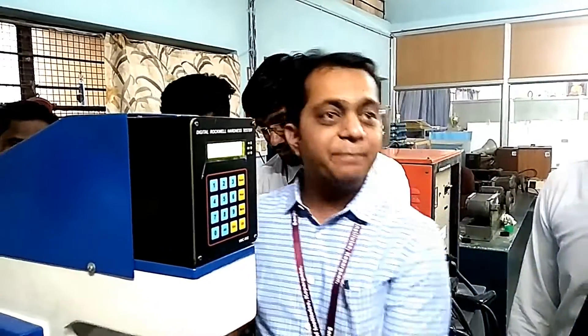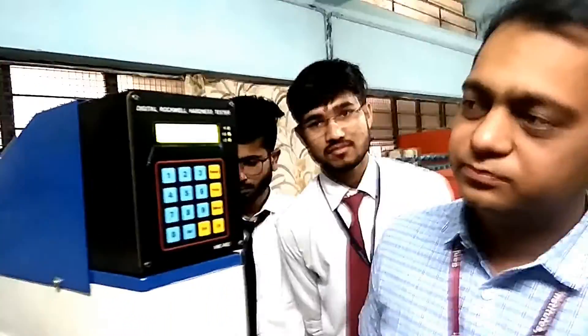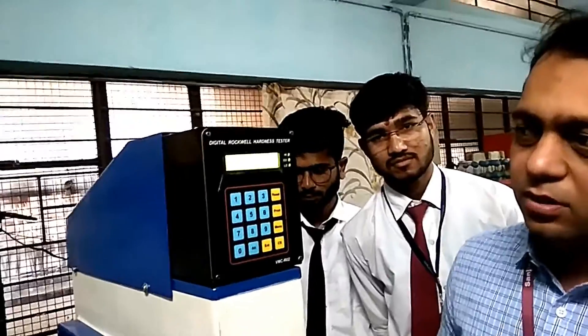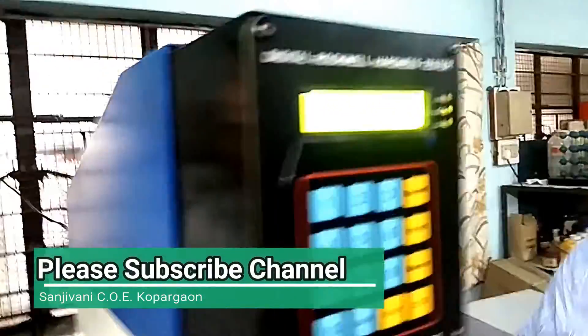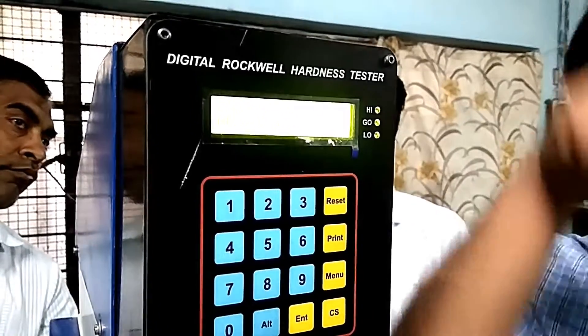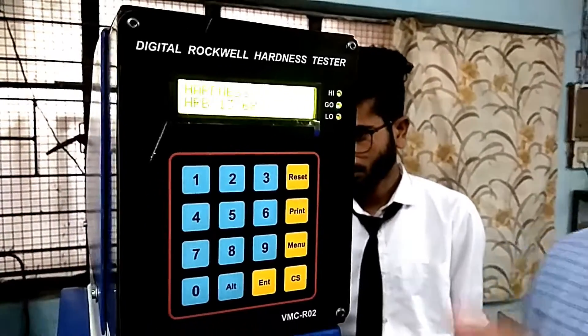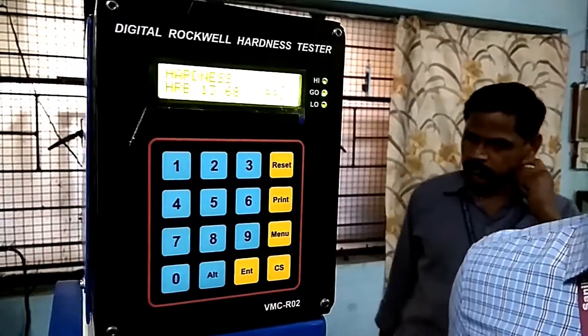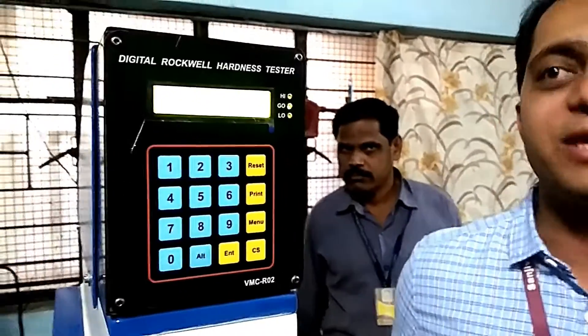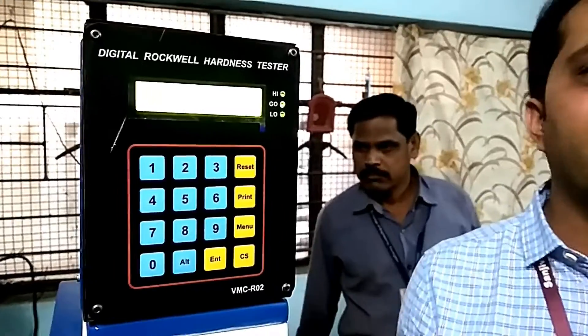Now we apply the major load of 100 kgf. Penetration starts inside the specimen. Once the penetration is complete, a beep is provided. Now we remove the load, and whatever value we get is the hardness value for the specimen. For the hardening specimen, the value is 99.1 HRB — that indicates 99.1 hardness value on the Rockwell testing machine with scale B.